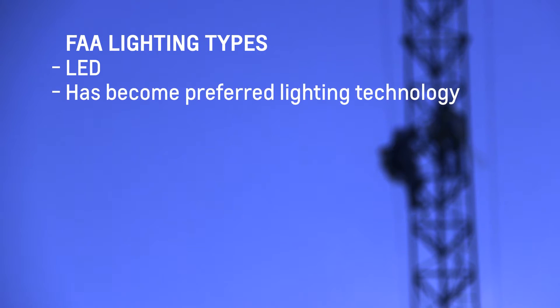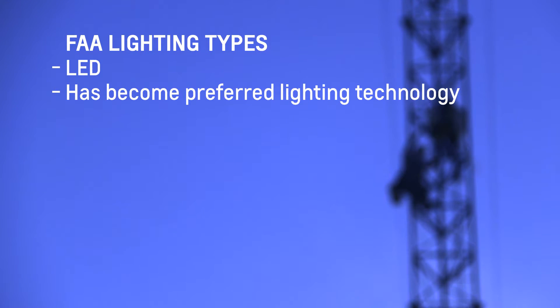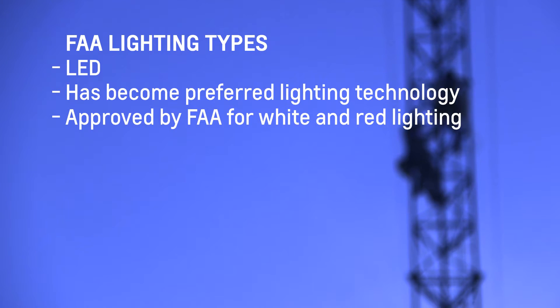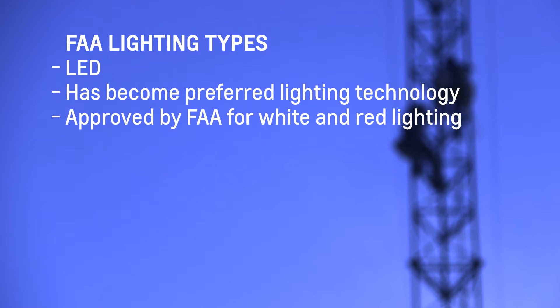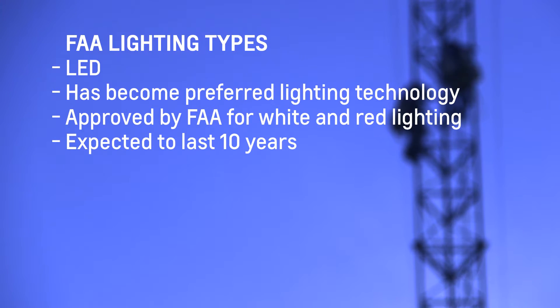LED. In the last few years, LED has become the preferred tower lighting technology because of lower maintenance cycles, superior optics, efficient power consumption, and longer warranty. LED is approved by the FAA for white and red lighting. LED flash heads are expected to last 10 years before a replacement is required. The latest LED systems have more efficient LEDs and improved surge protection. The new FAA advisory circular became effective December 4, 2015.